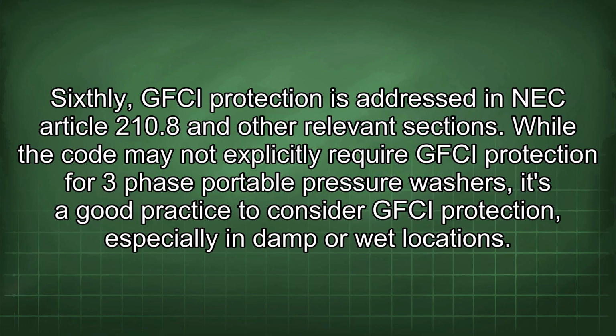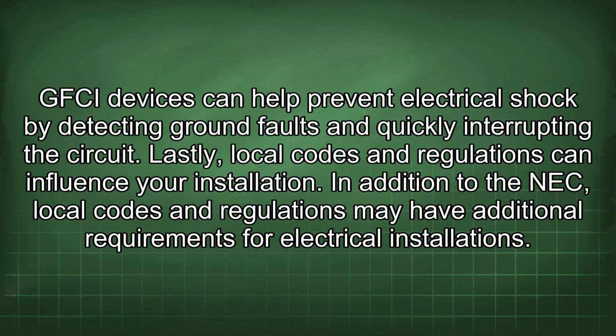Sixthly, GFCI protection is addressed in NEC Article 210.8 and other relevant sections. While the code may not explicitly require GFCI protection for three-phase portable pressure washers, it's a good practice to consider GFCI protection, especially in damp or wet locations. GFCI devices can help prevent electrical shock by detecting ground faults and quickly interrupting the circuit.